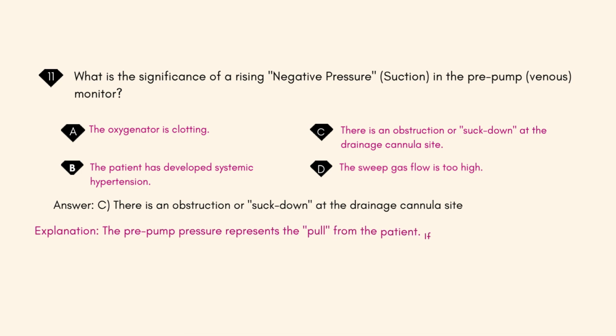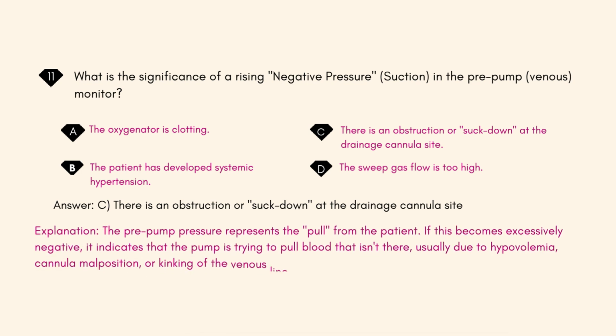Explanation: the pre-pump pressure represents the pull from the patient. If this becomes excessively negative, it indicates that the pump is trying to pull blood that isn't there, usually due to hypovolemia, cannula malposition, or kinking of the venous line.